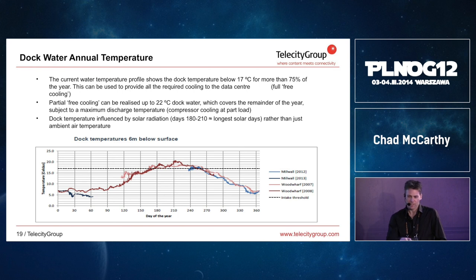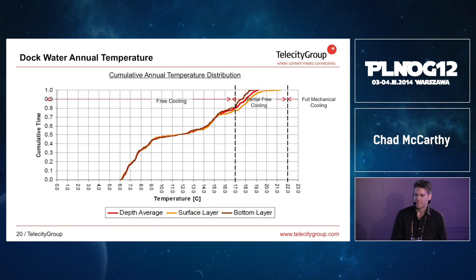The reason for this significant increase in temperature really brings us back to the fact that this is a stagnant body of water. And the largest contributor is the solar effect. If we look at the cumulative temperatures, which is the next diagram, here we can see the proportion of the year during which we have free cooling. We have a proportion of the year where we have partial free cooling. And as you can see on the right-hand side, we would never require full mechanical cooling. So there's an enormous reduction in the amount of mechanical plant that we would require for the data center.